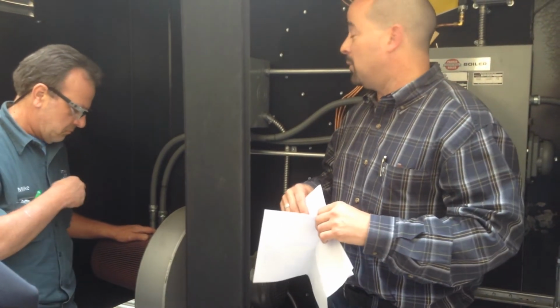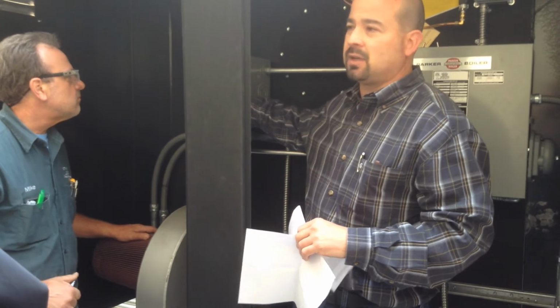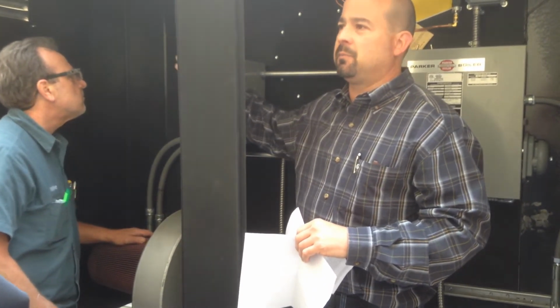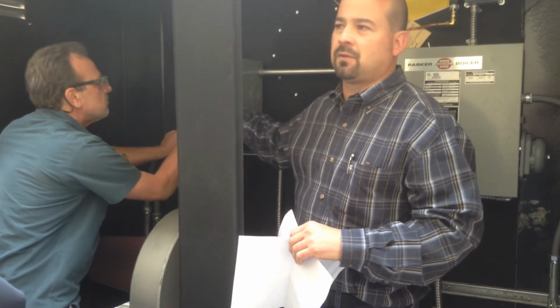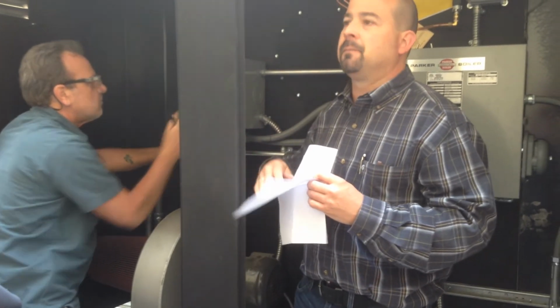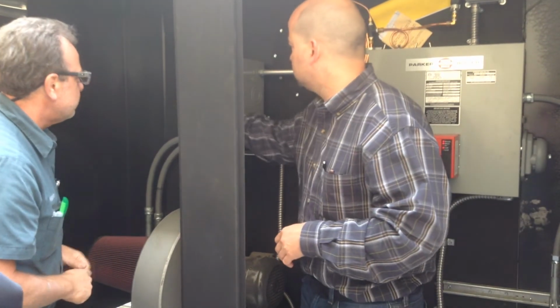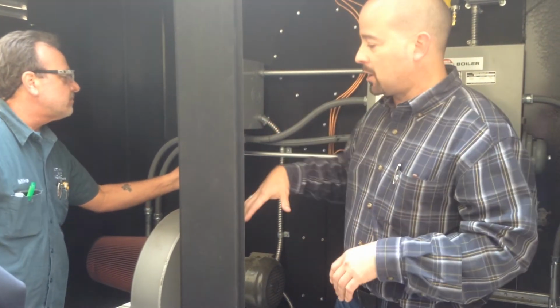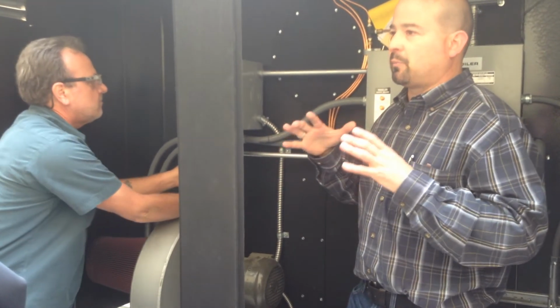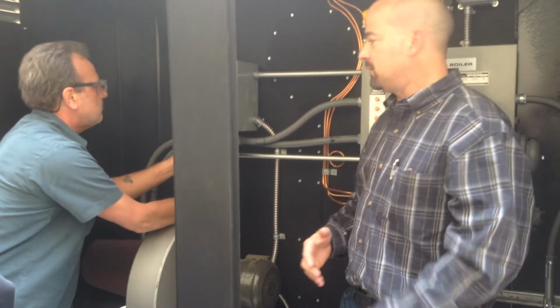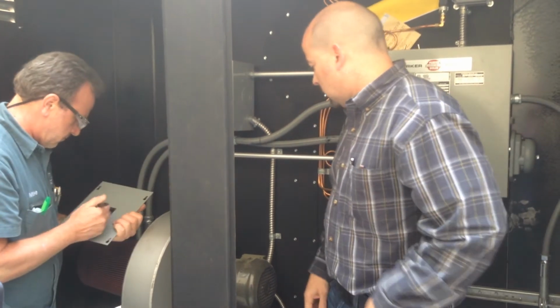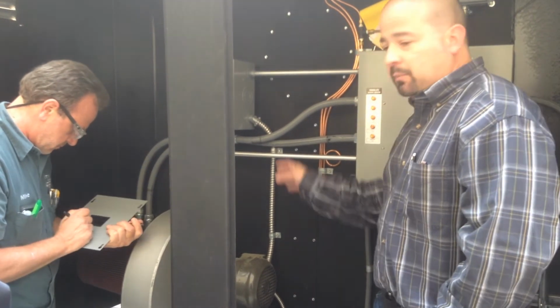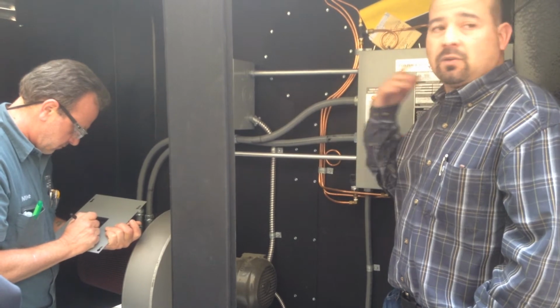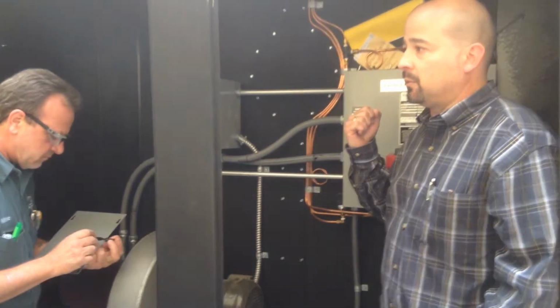The other thing is, more than likely you won't have to do anything but take out this EEPROM chip. Just take out the chip, put the new VFD in, pop the chip in, and it's already pre-programmed. Oh, okay, so it'll automatically download. Unless it gets wet. If the chip gets wet, then all bets are off. That's one good thing about Parker Boiler. They don't do a whole lot of proprietary controls. It's pretty much off-the-shelf stuff. So, okay, before I get into preventative maintenance, do you guys have any questions on the operation of what we just discussed?